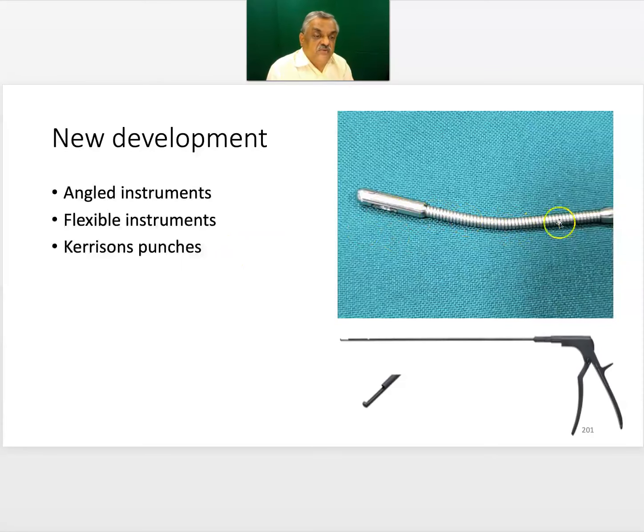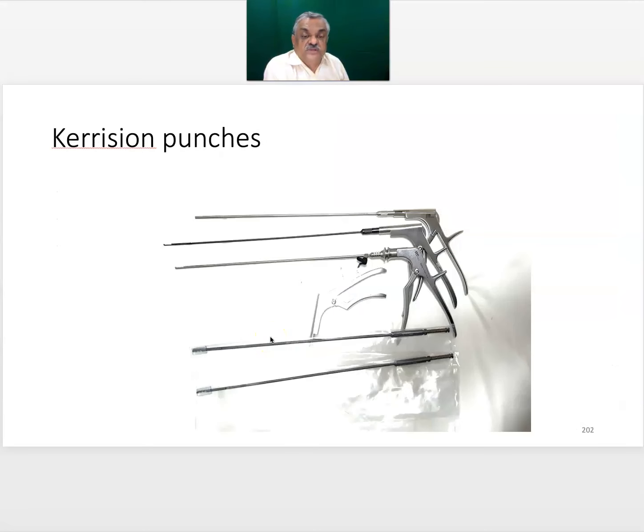Now these are having wires inside, and this is flexible, and you can give a shape to this instrument as per the requirement. Like for a down migrated fragment, you can literally make this instrument like this and go for the fragment. The flexible instruments, the angled instruments are the articulated instruments, where a knob on the instrument will help you in changing the angle of the tip. The Kerrisons, which are standard equipment from our open surgery, are also available, which go through the scope and help us in removal of the bone.